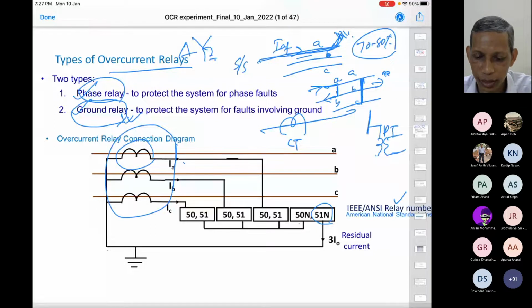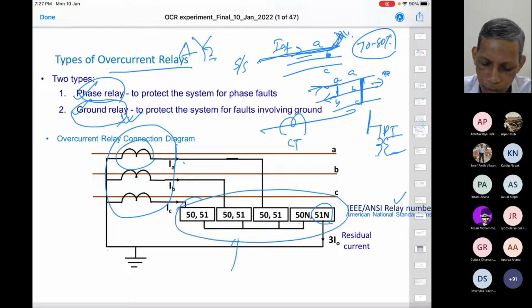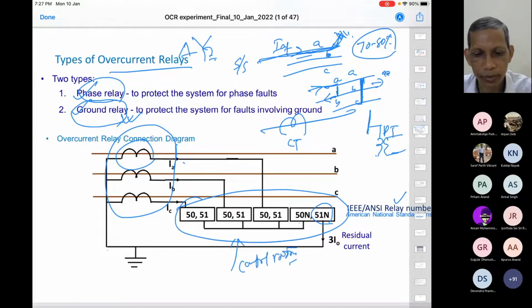You put the CT at the particular location where you would like to measure the current. The wirings are taken from that system, from the transformers or wherever you're measuring, or the bus, to the control room. The control room will have several relays. Hundreds of relays may be there in a big substation, maybe thousands, to take care of different protection perspectives, and these are nothing but numerical relays.